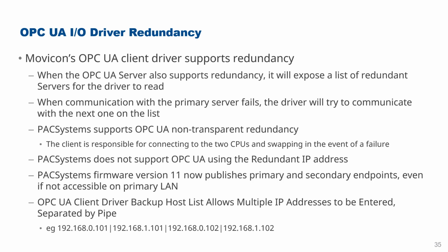Now, PAC Systems does have a redundant IP address, but the redundant IP address doesn't support OPC-UA. So what you would need to do there is, if you wanted to use the redundant IP address, you could use the older Emerson Ethernet protocol, or you could use Modbus TCP. They do support the redundant IP address. But for OPC-UA, you don't use that, you use that non-transparent redundancy.